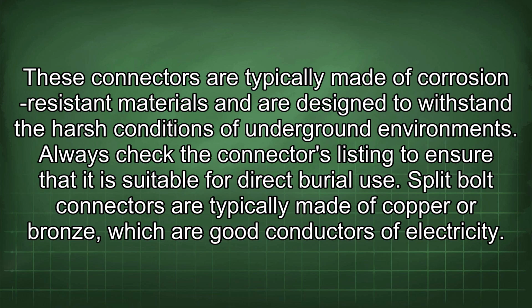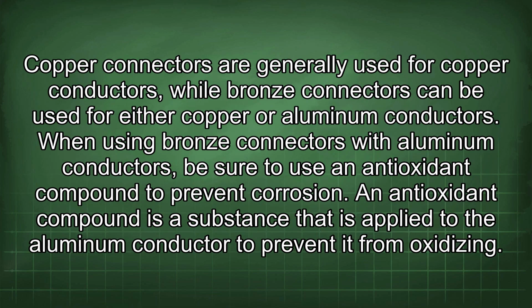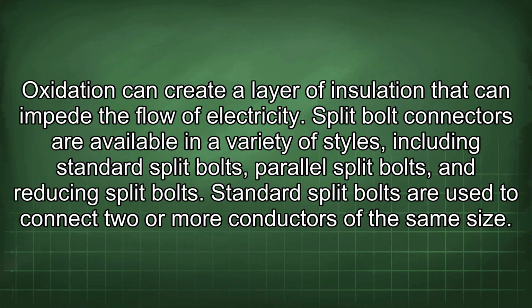Split bolt connectors are typically made of copper or bronze, which are good conductors of electricity. Copper connectors are generally used for copper conductors, while bronze connectors can be used for either copper or aluminum conductors. When using bronze connectors with aluminum conductors, be sure to use an antioxidant compound to prevent corrosion. An antioxidant compound is a substance that is applied to the aluminum conductor to prevent it from oxidizing. Oxidation can create a layer of insulation that can impede the flow of electricity.